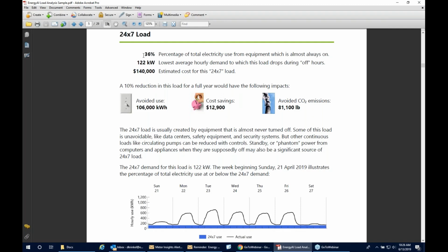They have to have ventilation running 24/7, but this number often surprises people, unless it's a special facility like those I just described. If this is 60% for a standard office building, then usually there's some easy pickings for savings there.